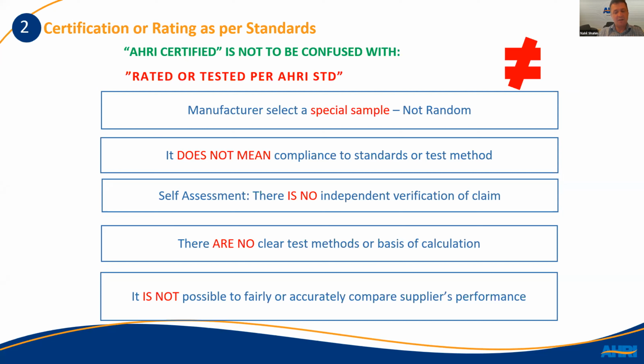When you say I'm tested per AHRI or rated per AHRI, it's basically a manufacturer or any party that is picking a sample and testing it in a non-AHRI approved lab. So the term again can be misleading. The unit that is chosen may not be a manufactured unit. It's not a randomly chosen unit, as AHRI does when they do annual testing for certification. So it may not represent the products that are being manufactured today.